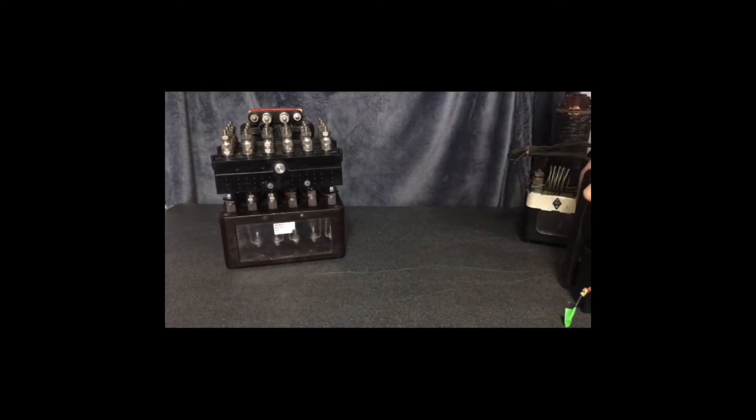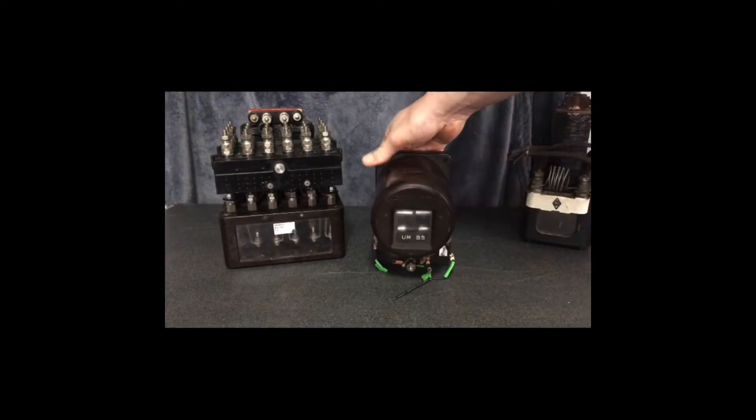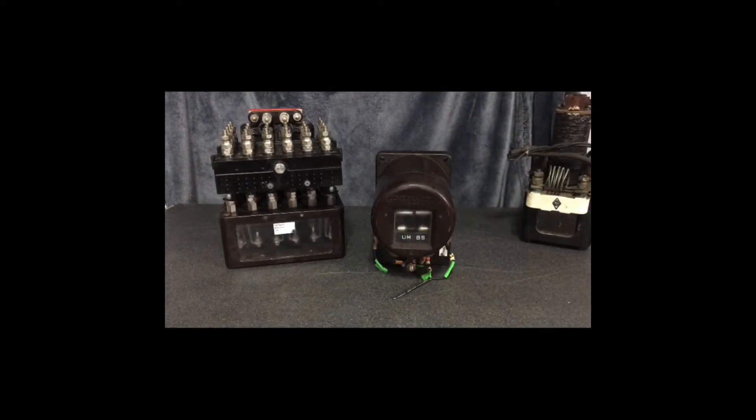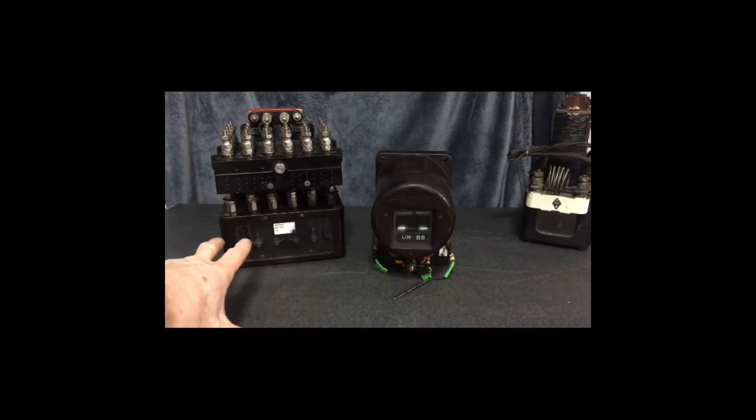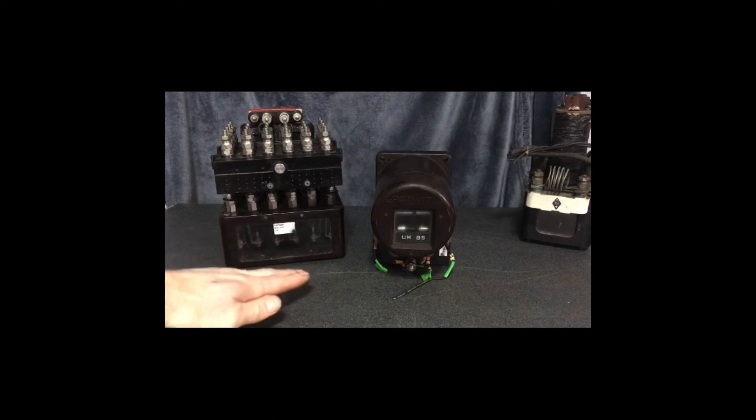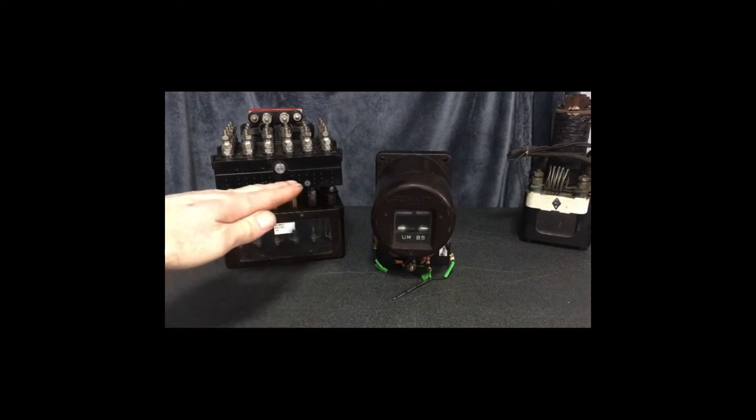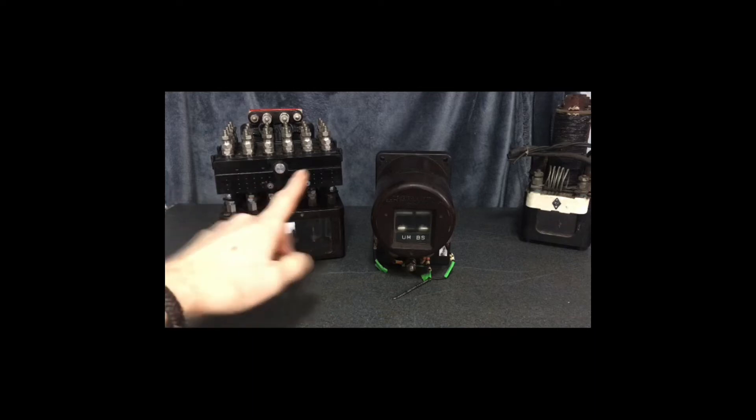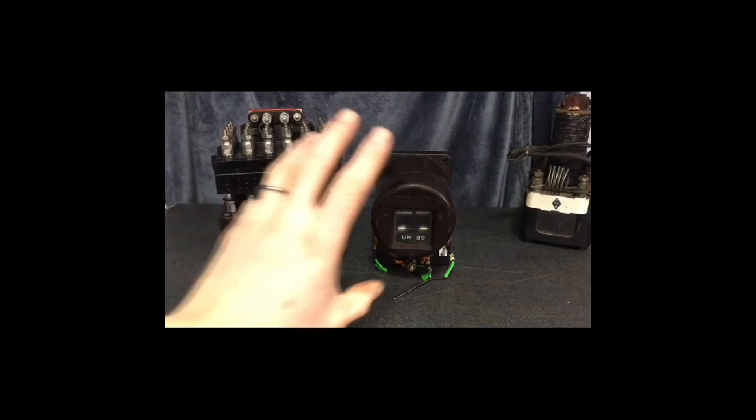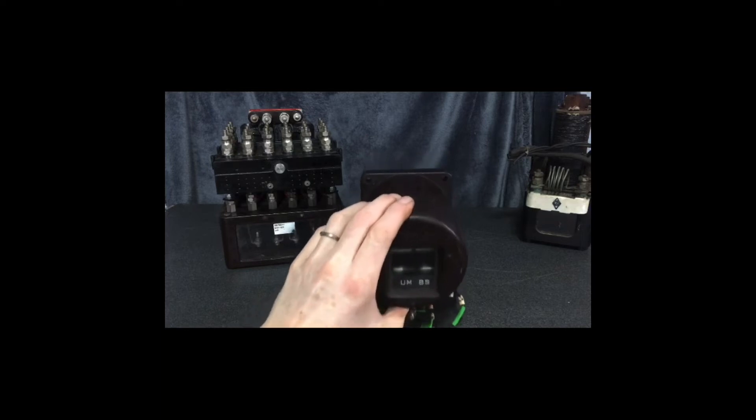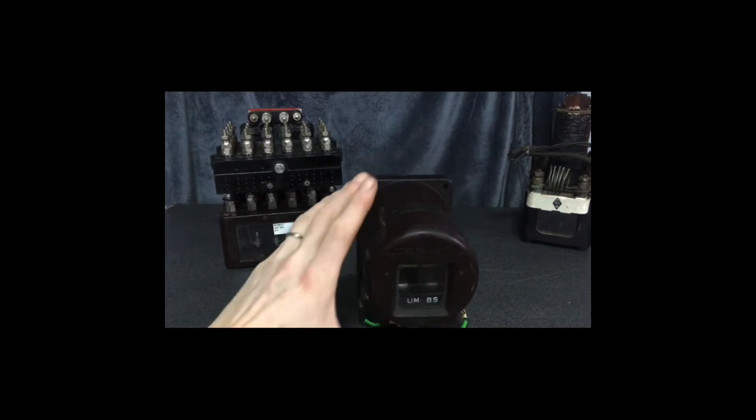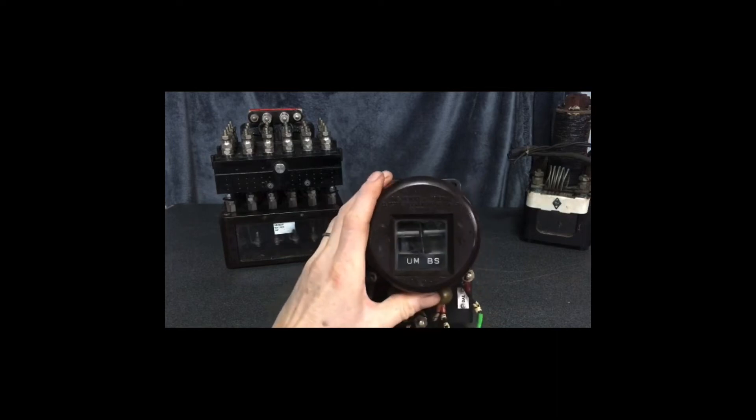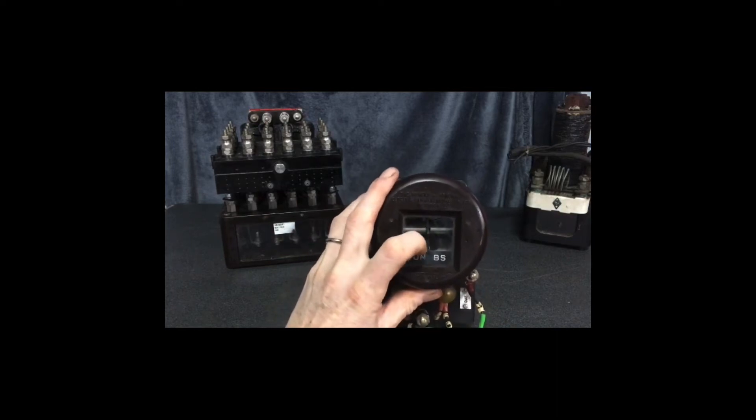The last one in the polarised series I'd like to show you is this one. This is a polarised relay. These relays, as you can appreciate, these are neutral relays. All these do when you apply voltage to them is their contacts energise, and when you take the voltage away they de-energise, so they go up and down, they make and break. This one's a little different. This one works with a magnetic field. There's three ways this can work. The first way is you take the power off and it automatically fails back to its sprung-loaded position.